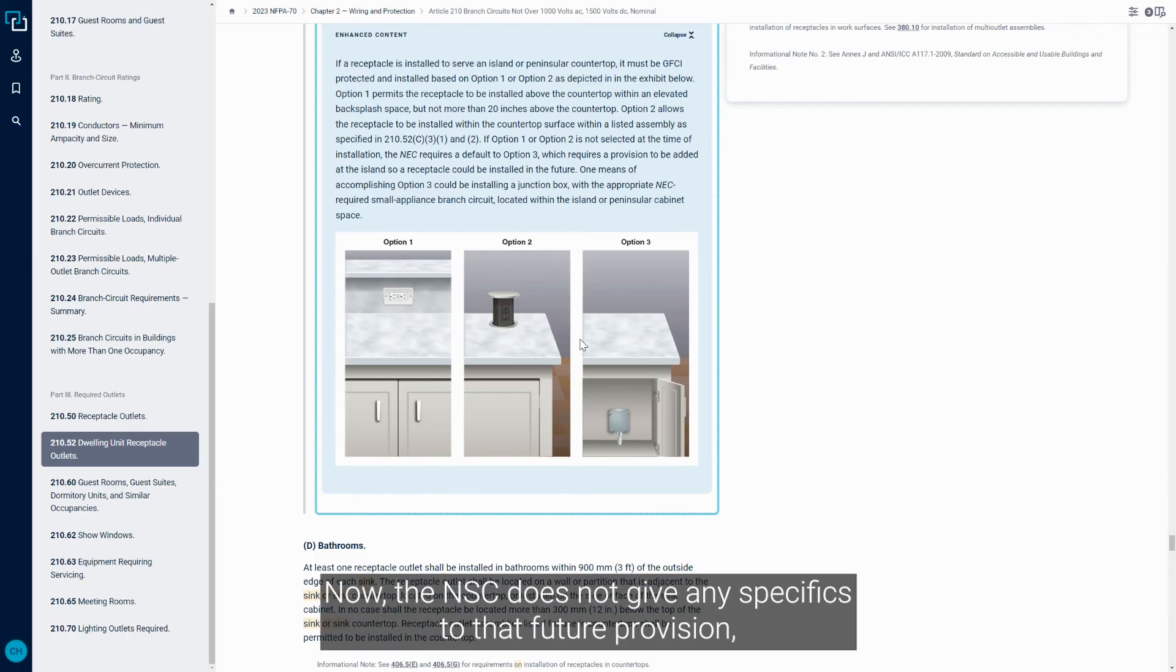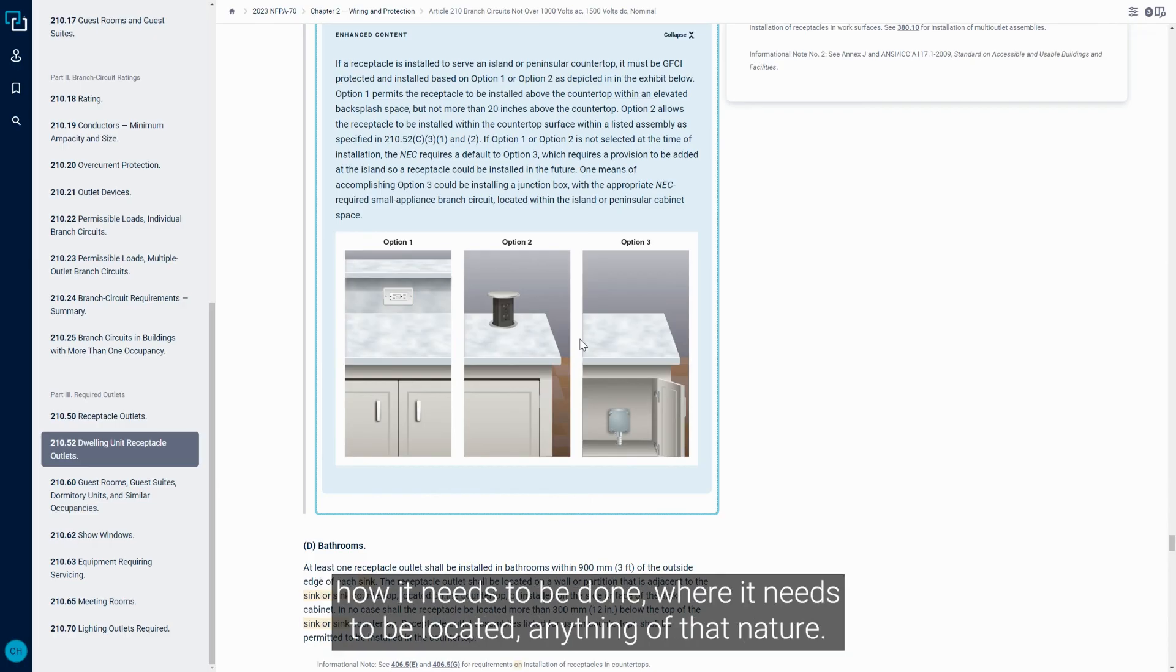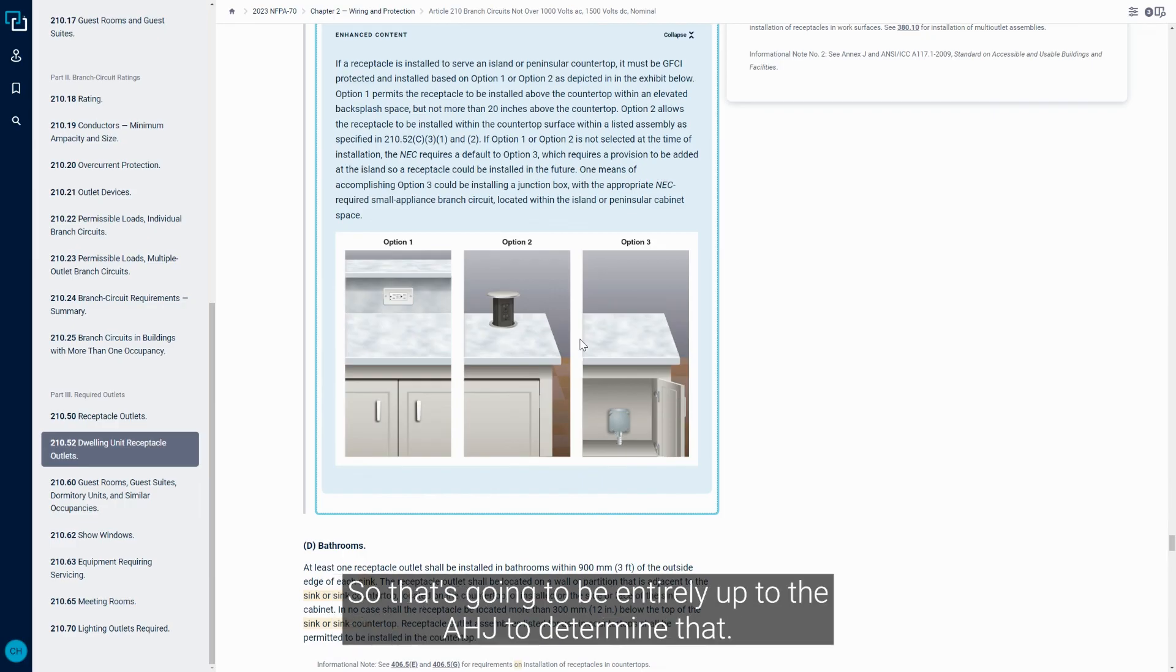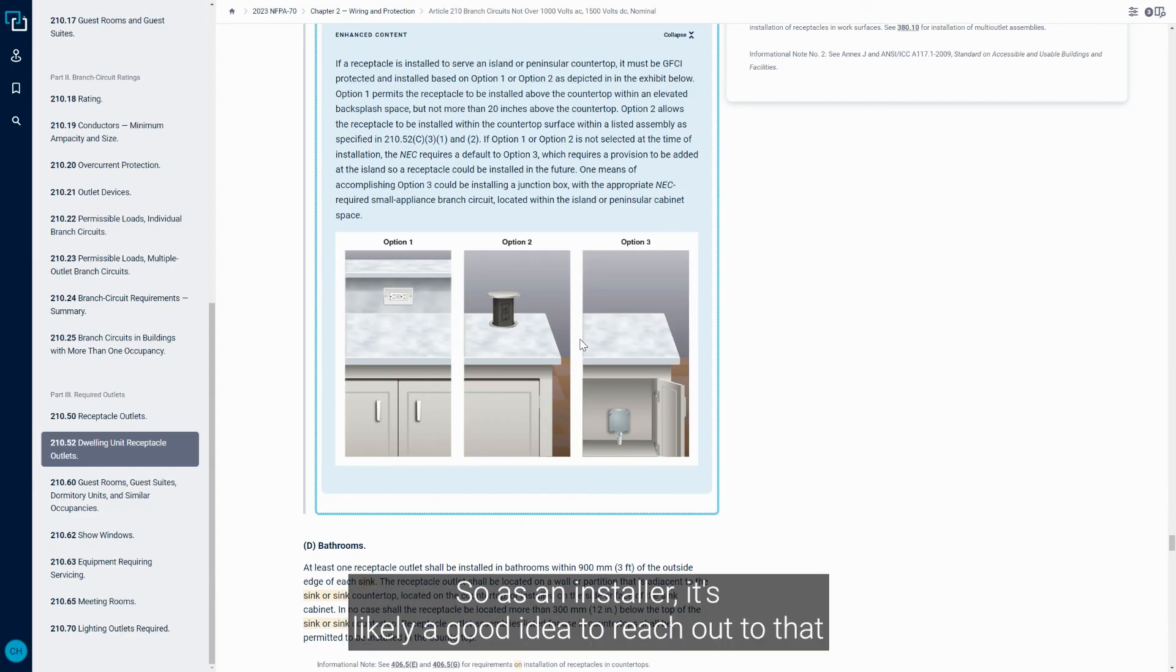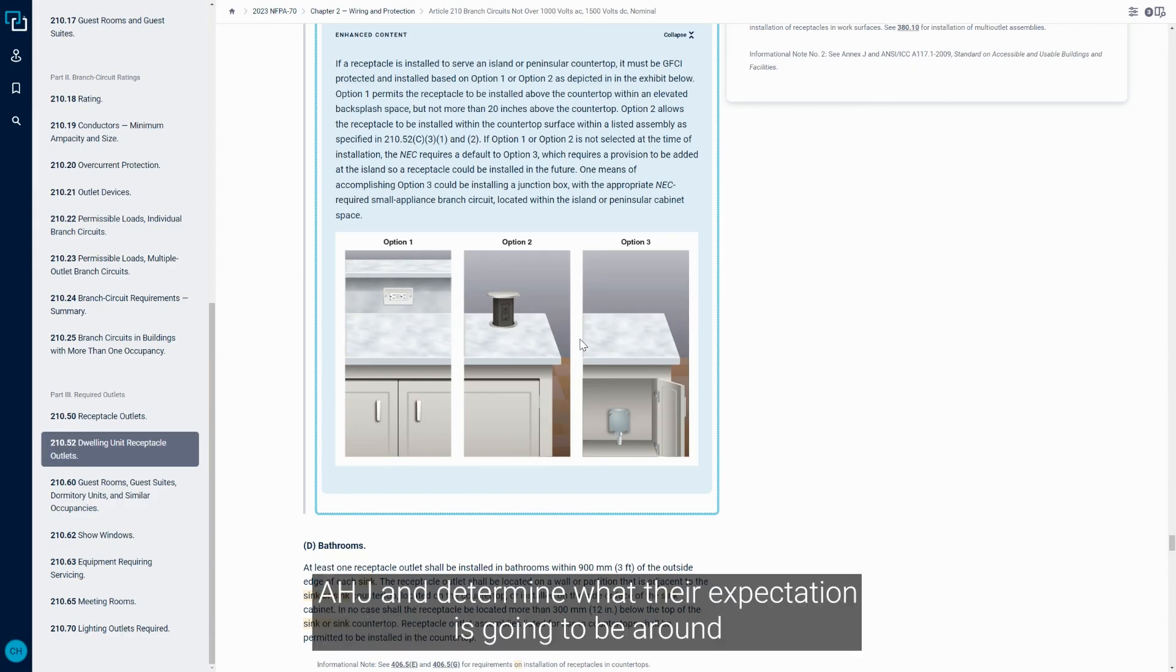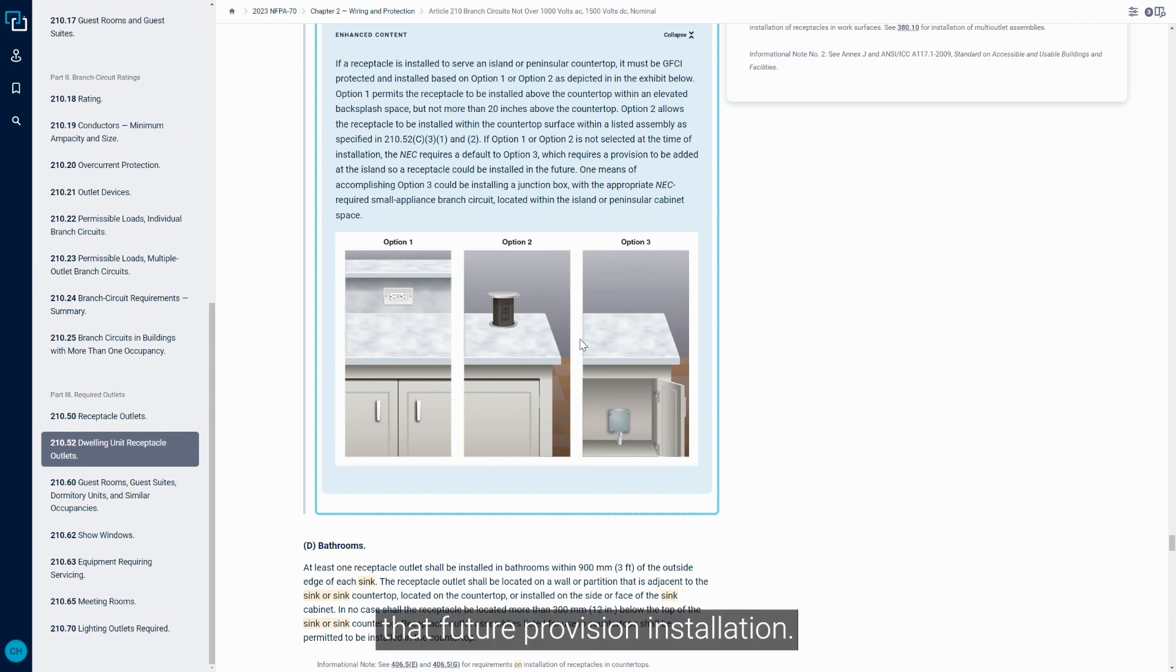Now the NEC does not give any specifics to that future provision, how it needs to be done, where it needs to be located, anything of that nature. So that's going to be entirely up to the AHJ to determine that. So as an installer, it's likely a good idea to reach out to that AHJ and determine what their expectation is going to be around that future provision installation.